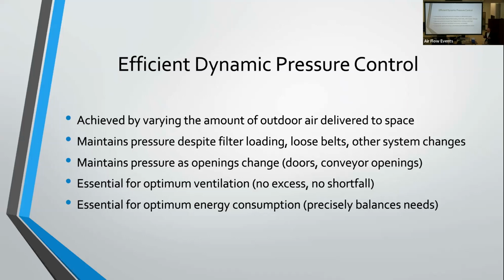So you're not talking a lot of static pressure. Those negative results from negative pressure spaces are in the same area. You start to see a lot of those problems when you're at the 0.0, 0.02 negative pressure spaces. So 0.01 to 0.02 inches of positive pressure in that space is really all you're trying to do. So how do you do this? How do you achieve this dynamic pressure control? Well, all you're doing is varying the amount of outside air that's being delivered to the space to maintain that optimal 0.01, 0.02 efficiency.